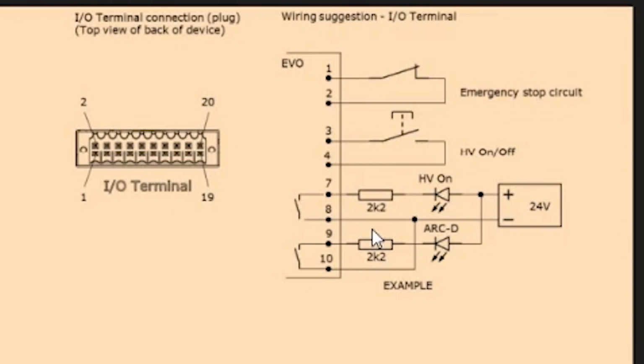But here, let's talk about pins 1 and 2. This is an emergency stop circuit. It's very low current, very low voltage, and normally closed. Our customer was wondering if they could create not only a door interlock for their high voltage cage so that the power supply will automatically shut down when the door is opened, but also have a secondary switch that's an emergency stop button in the control room itself. Both of these would automatically shut down the unit.